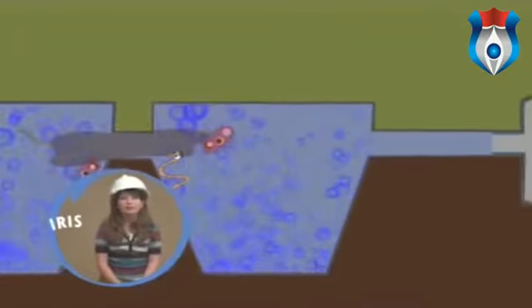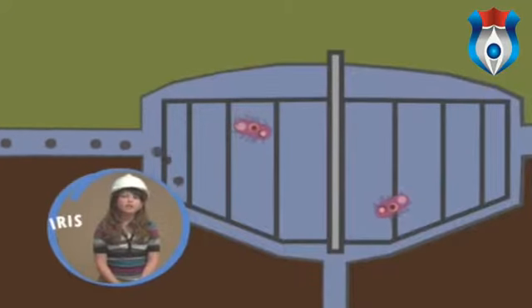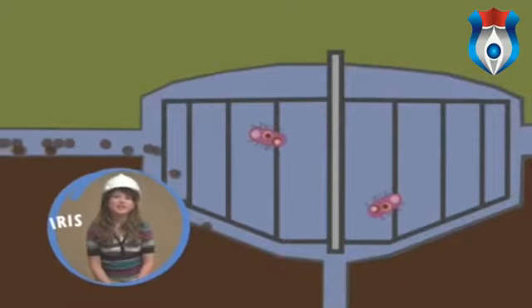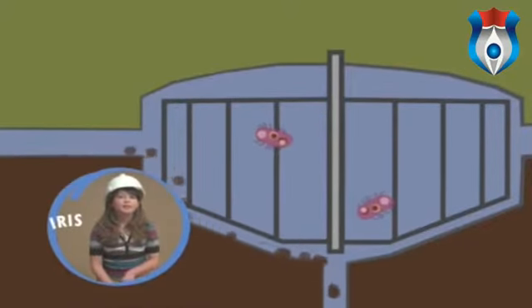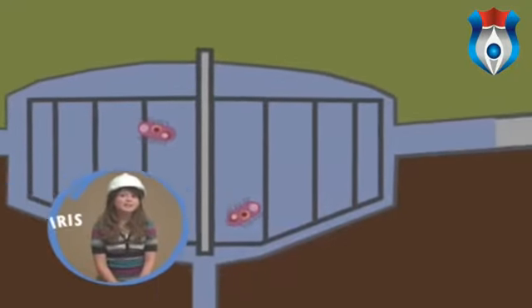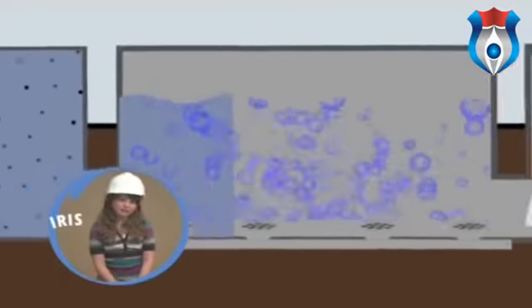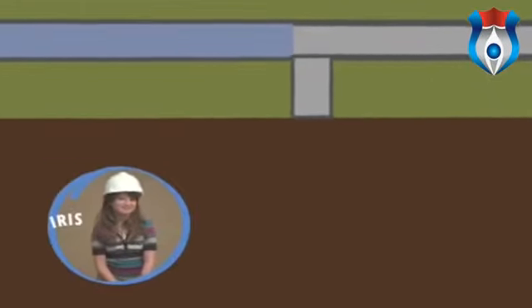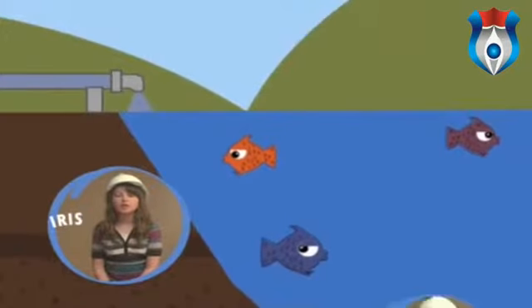After that, the wastewater goes to the final settling tanks. Most of the good bugs in the wastewater get recycled back to the aeration tanks. The rest settle with the activated sludge at the bottom of the tank so it can go to the digesters. Sometimes the treated water can go on to be filtered, disinfected with chlorine and or ultraviolet light. The treated wastewater is discharged to the waterways or can be used by industry.